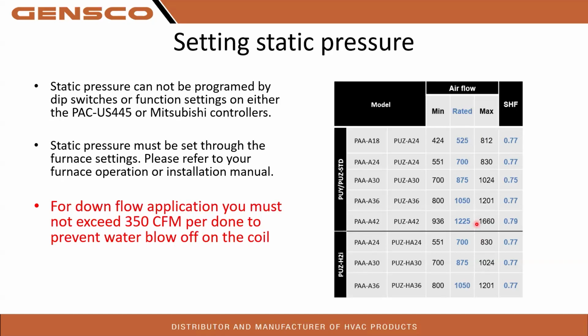If you're doing a downflow application, do not exceed 350 CFM per ton, or you will be blowing water off that coil. I had one of these things just recently, a 3-ton system, water blowing off in the base pan. I asked them what was your airflow set to. They said 1200 CFM. Well, 400 times 3, that's 1200 CFM. Max in that situation would have been 1050. So they had airflow issues, which is what was causing that to happen. So it's not just a recommendation, it will blow water off that coil, guaranteed. So again, this little chart right here, you will find this in your installation manual. And downflow, very important. Do not exceed 350.